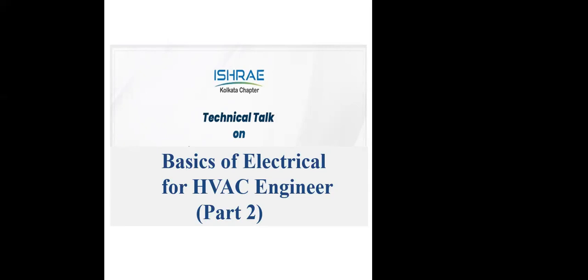And if you remember, in the last session I discussed the fault level of the systems. In some cases it is 65 kiloamperes, in some cases it is 50 kiloamperes, like that. Now the entire fault system is not in place unless we find a path. In case there is a fault, a short circuit, or lightning, where will this fault current go? It will affect the entire system, and it can be very fatal. So although it is a little offbeat subject, as far as safety and protection is concerned, it is utmost important. And I want that everybody follows this.